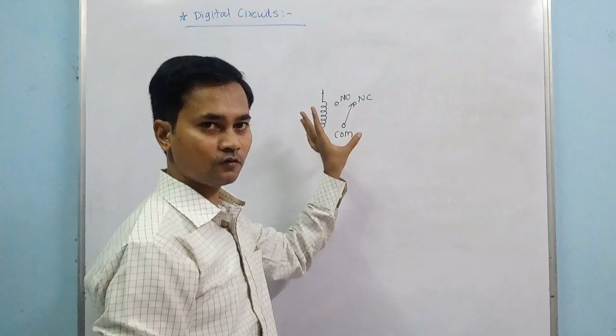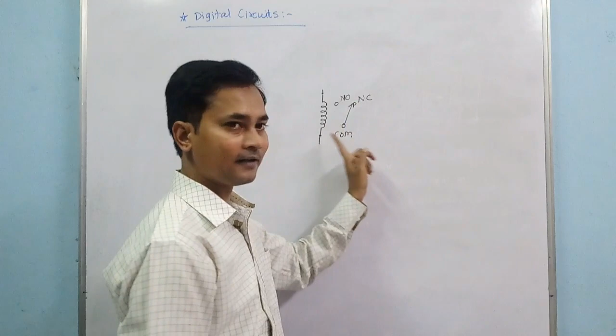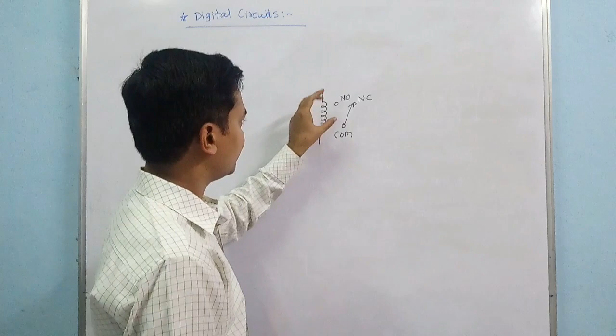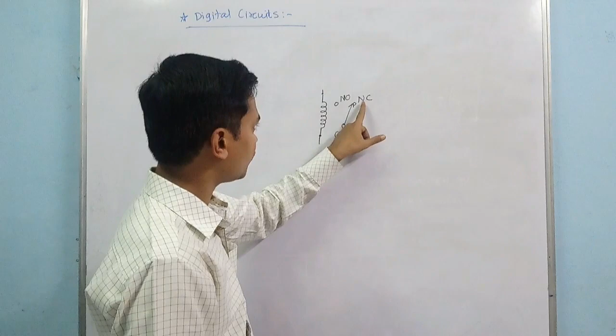If you purchase a relay from an electronic shop, you may have this sugar cube relay. If you check it with a digital multimeter, put the multimeter onto continuity so that you can check whether the path is there or not for the current flow. If you connect the multimeter probes across these 2 points, you will find there is continuity, and the beep sound will be audible. Then if you connect the 2 probes across common and this point, you will not hear any sound. That means these 2 points are open, not shorted. These 2 points are always connected, that's why the name is given normally closed, and this point is not connected always, that's why the name is given normally open.